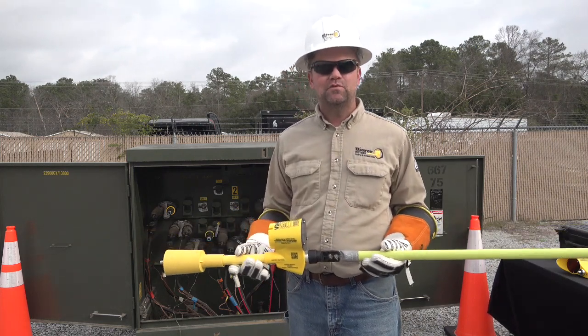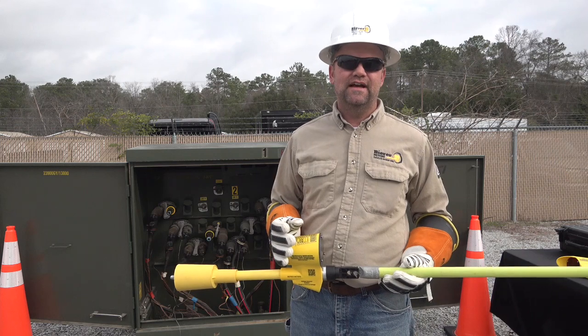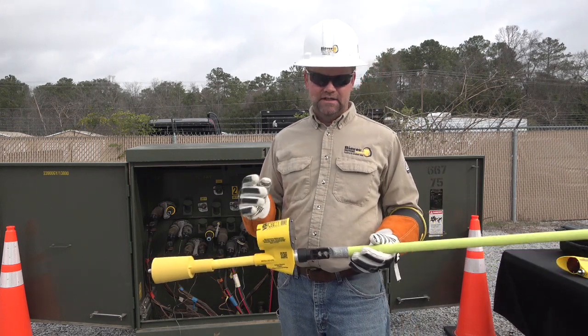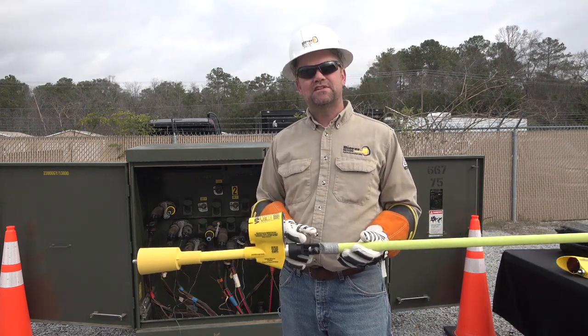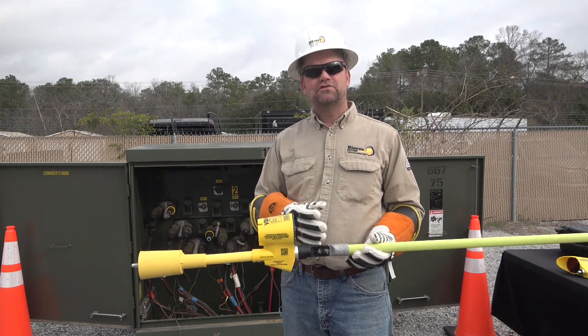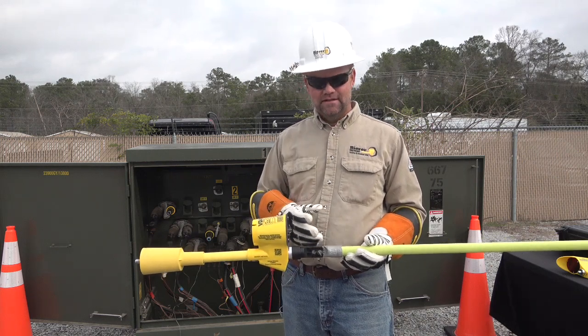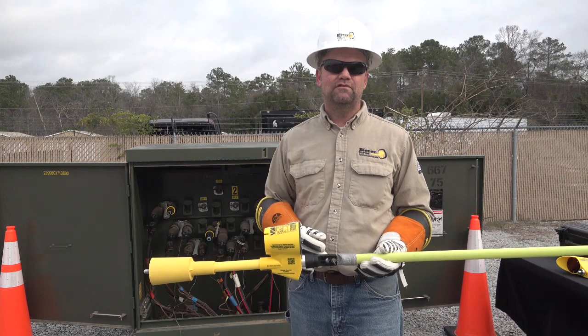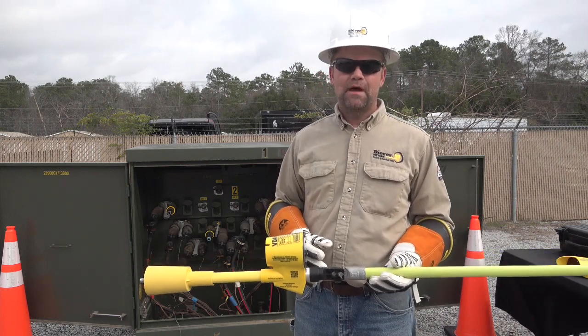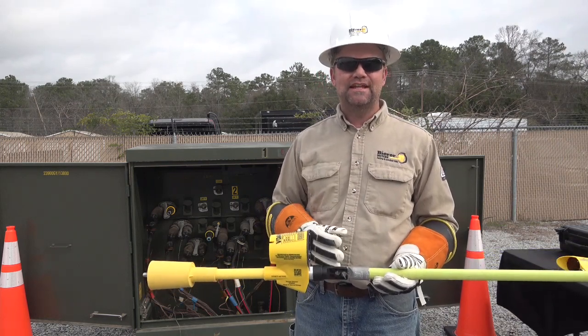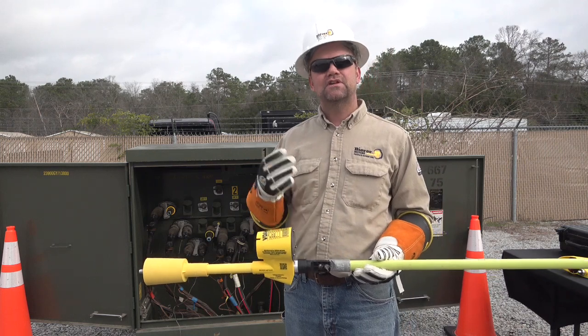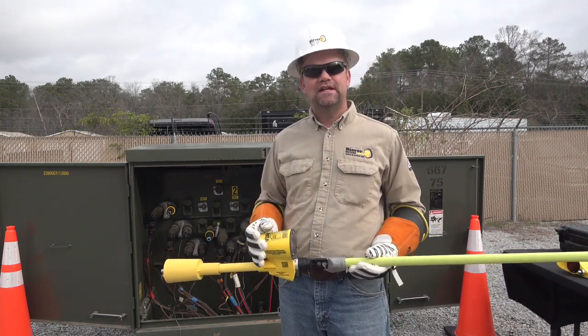Bierer highly recommends whenever you're using a single point device such as the VDAH300 that you do not use metal accessories and a large metal surface out here on your stick. This metal surface here is relatively small, but just remember, the more metal you add to the end of the device here, the more it's going to couple and the higher the reading.